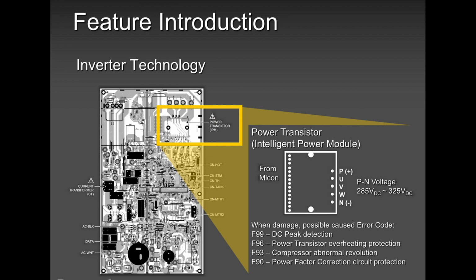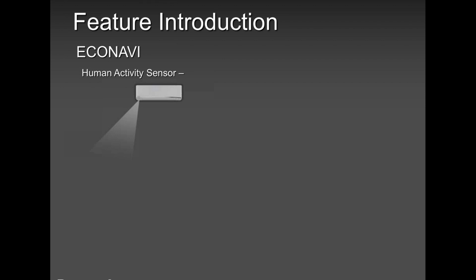He said, I already did that. I said, you did it for how long? He said, I did it for around 3 to 5 minutes. I said, no, it's not enough. So always remember, when you get this kind of error codes, give it time. Give it time to cool down. Give it time to discharge all the capacitance. Okay? So after he reset the power, I checked with him and he said, yes, it's up and running, it's fine. So most of these error codes related to the power PCB at the outdoor unit, if you reset it for 15 minutes, it can come back to life, and it may work very well with no issues whatsoever.